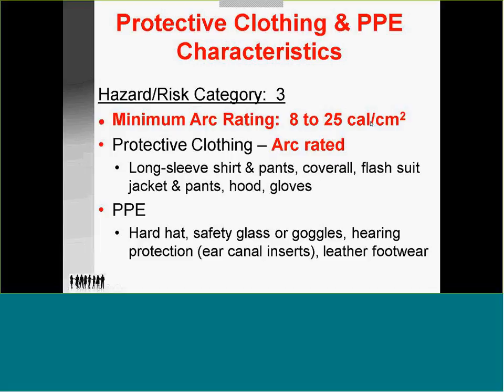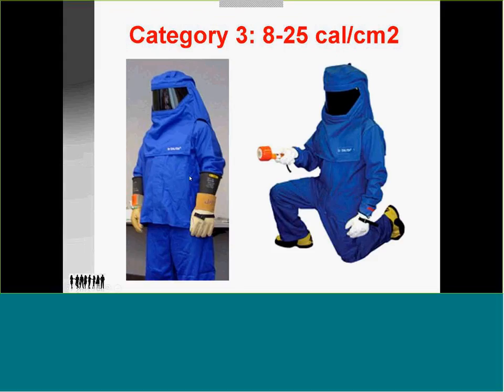Category 3 is 8 to 25 calories per square centimeter. Now you need a long sleeve shirt, pants, coveralls, flash suit, pants, hood, and gloves. We're layering. Glasses, hearing protection, and the gloves must be rated for going above 8 calories. Category 3 suit, usually they're color-coded. Blue is a category 3; green, gray, or green-gray become category 4.